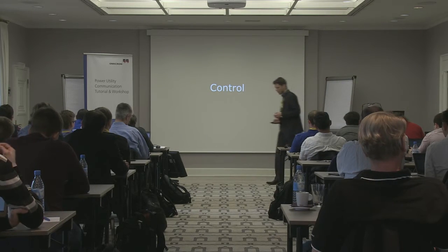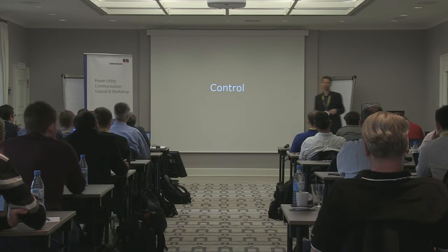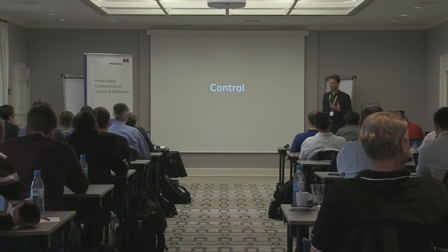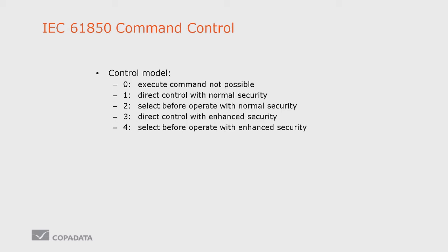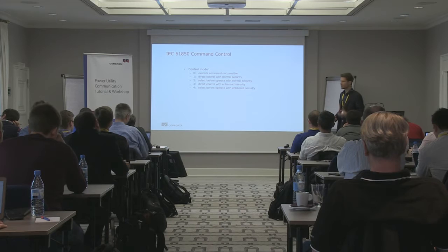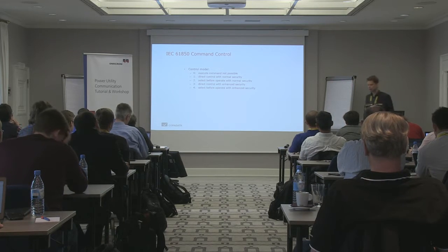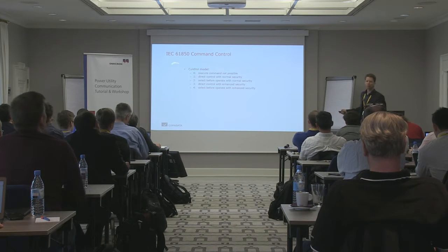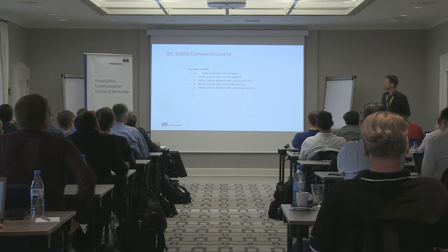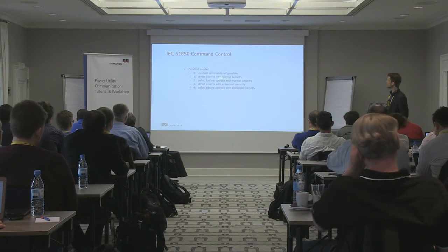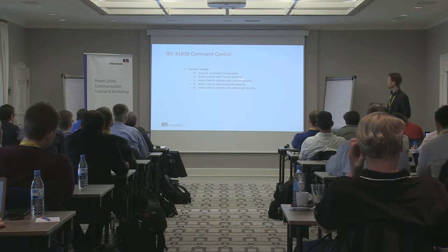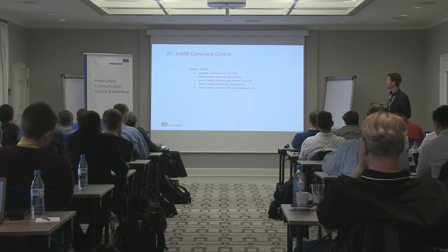This is about engineering. Now just a few words about control, because as I said, it's a little bit of uniqueness dedicated to the client — although the server is executing it. When we talk about command control in 61850, we very early understand that there are different control models. There is control model zero, which means uncontrollable. But then there is one, two, three, four. Direct control is here, then we have normal security, and select before operate.